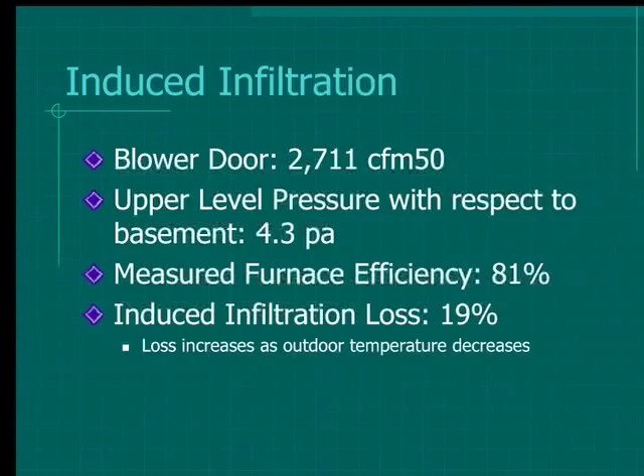Remember we talked about one piece of paper moving air, so now we've got 4 pieces of paper moving air. What this furnace was doing, every time it came on, was sucking in outside air through the cracks in the basement and exhausting this air out the cracks to the attic or out the windows. It was running 81% efficient, so the loss was 19%. Basically that furnace was delivering 4/5 of what it should be delivering. 1/5 of that energy was going right outside, so a 20% loss from that. The problem was a leaky return system and an imbalance, in the sense that when you supply a room with air, you're positively pressurizing that room, and you need to provide a path for that air to go back to the furnace.